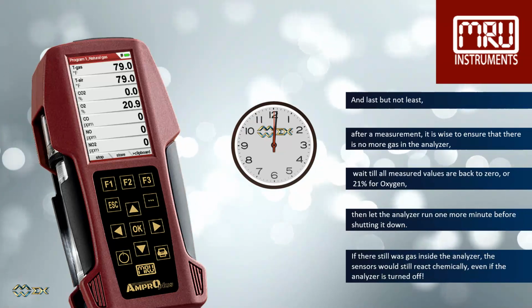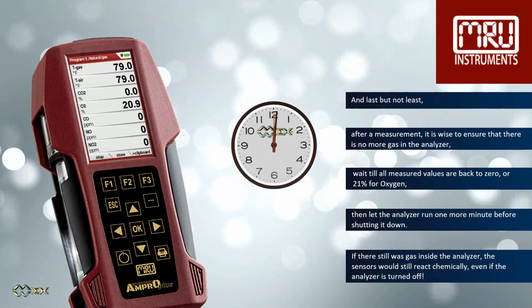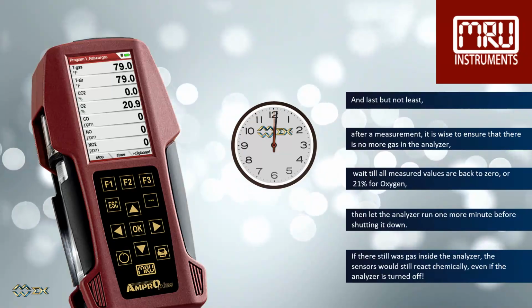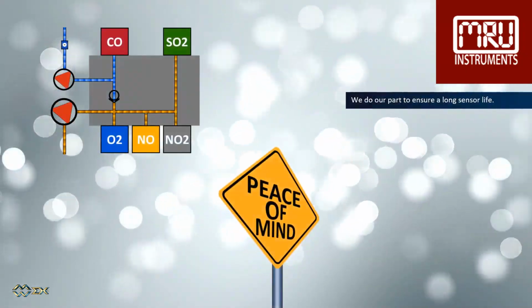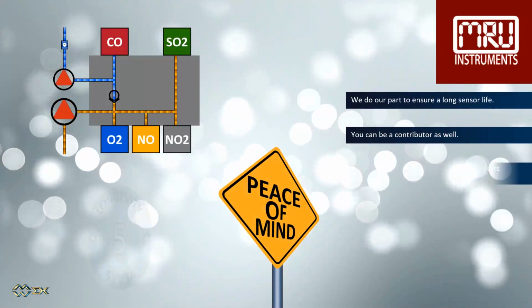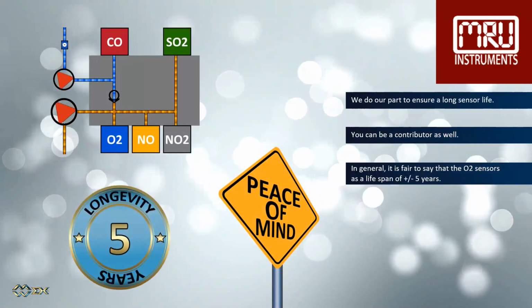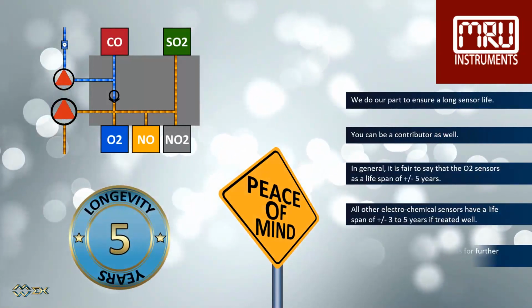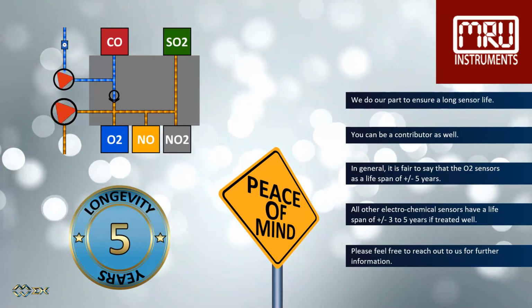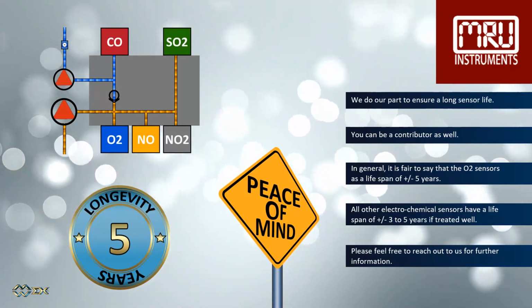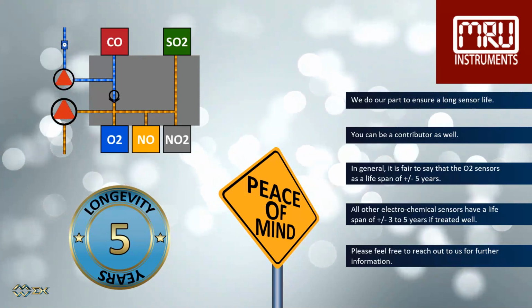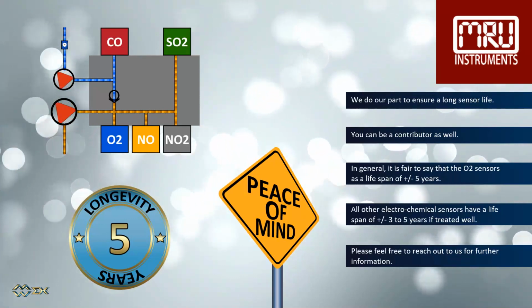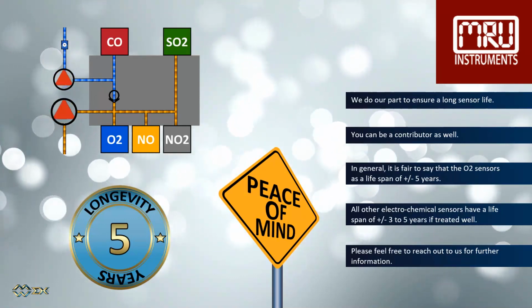Gas inside the analyzer will make the sensors react chemically, even if the analyzer is turned off. We do our part to ensure a long sensor life. You can be a contributor as well. In general, it is fair to say that the O2 sensor has a lifespan of plus or minus 5 years. All other electrochemical sensors have a lifespan of plus or minus 3 to 5 years if treated well. Please feel free to reach out to us for further information.